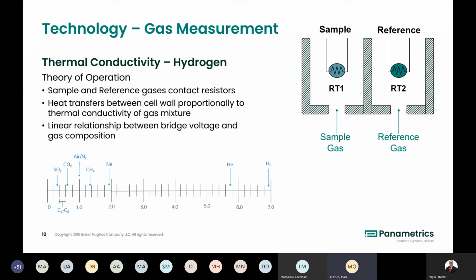you can see here, just moving to the other similar looking transmitter, but a completely different technology, and that is the thermal conductivity analyzer transmitter that we have, and this is the XMTC. So it uses the chemical property of gas called thermal conductivity. So different gases will conduct heat at different rates. So hydrogen has a very specific thermal conductivity value, and it's shown on the scale below there, and it's quite different from other gases, let's say CO2 or air.